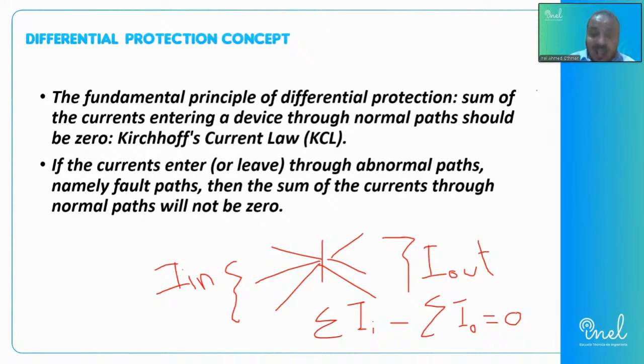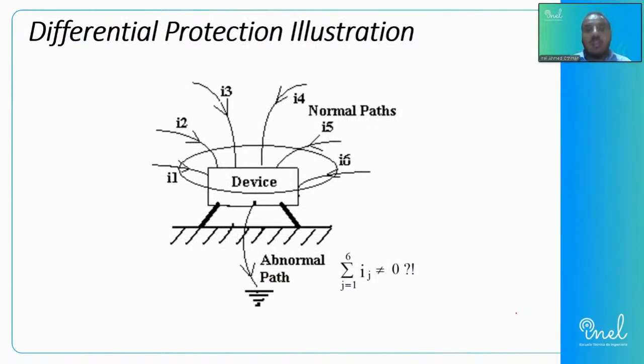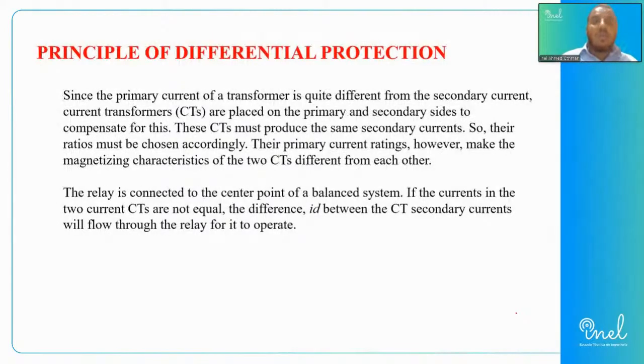If the system is balanced, the difference should be 0. But if there is a difference between I in and I out, the protection device should sense and act. The protection device that should act at such a moment is the differential protection concept, which has the responsibility, or is the major element, to act. So if we have a certain device and normal paths, normal operation will lead to the summation equal to 0, and abnormal operation will lead to a certain value for such a summation. That is exactly the principle of the differential protection.